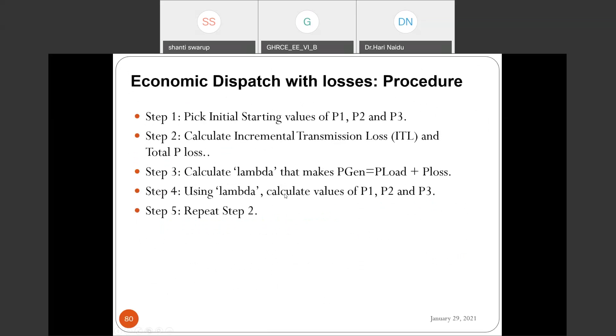Let us see each one. Step 1: pick the initial starting values P1, P2, P3. Because the load is 850, assume losses to be 0. P1 is 400, P2 300, P3 150. When you sum them, it is 850 megawatts. Even though the losses are not 0, assume losses to be 0 initially, so it is not correct.